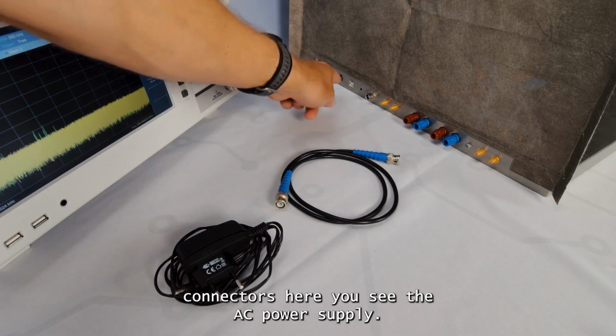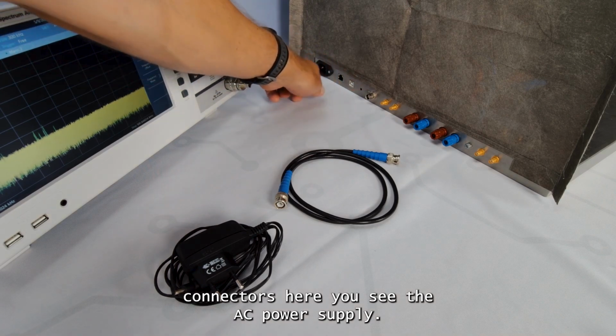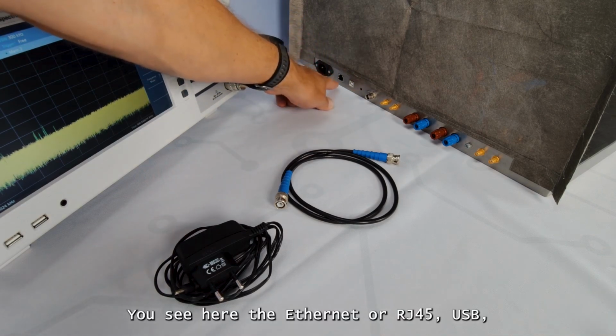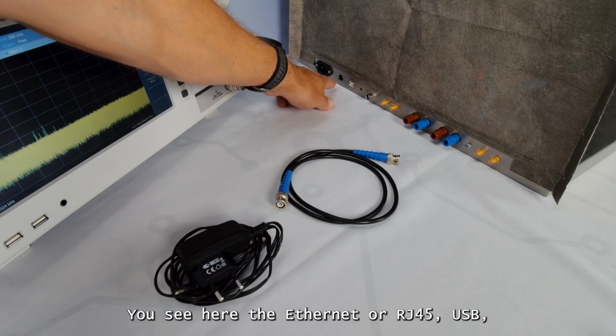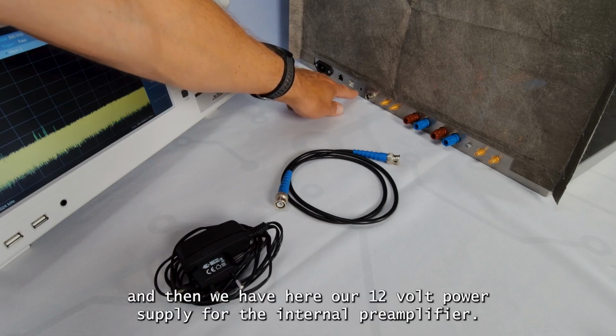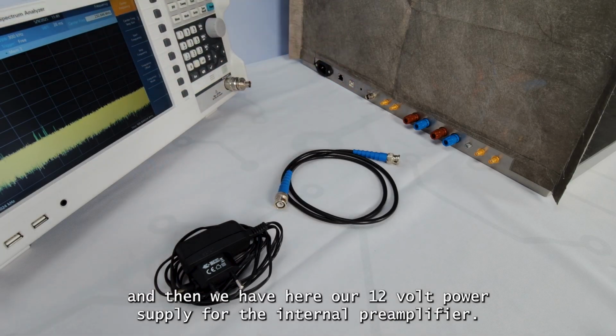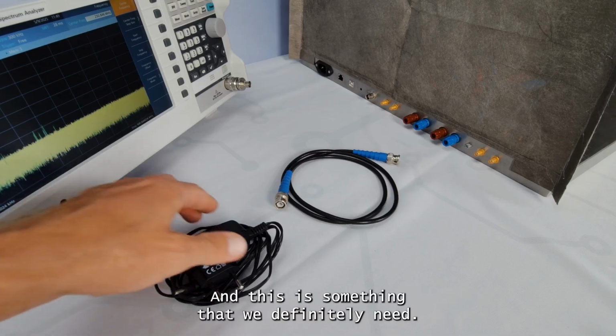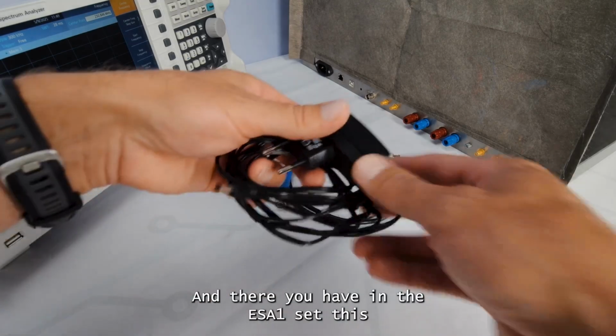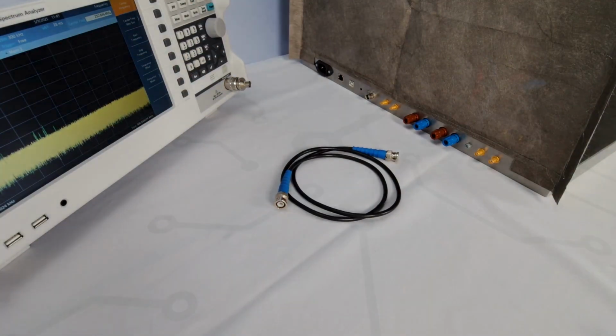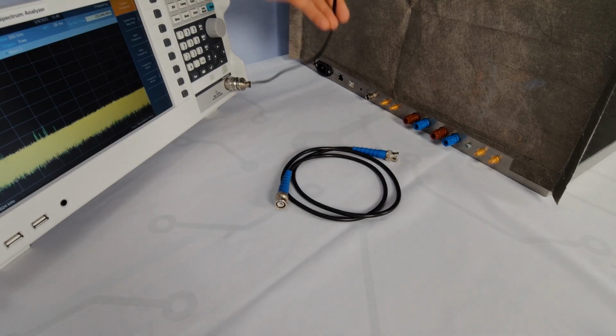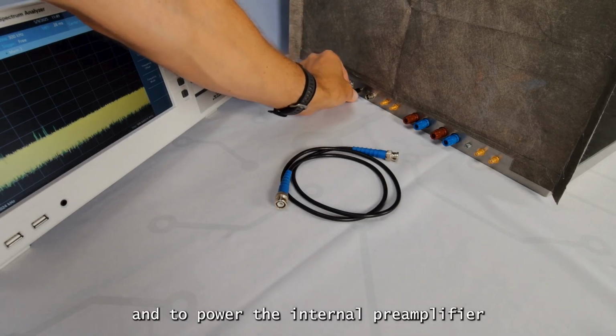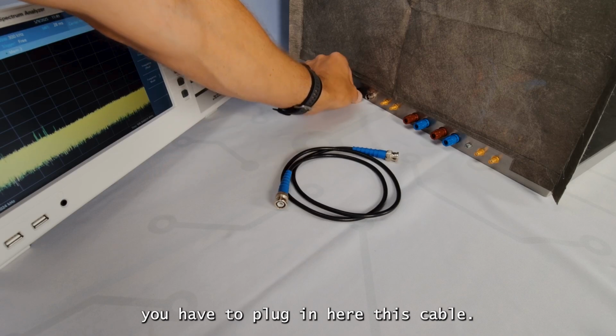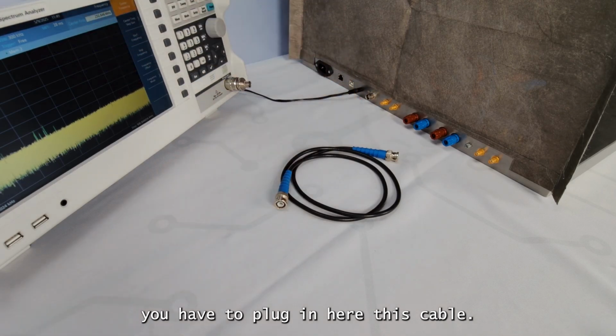For the connectors here, you see the AC power supply, you see the Ethernet or RJ45, USB, and then we have our 12-volt power supply for the internal preamplifier. And this is something we definitely need, and in the ESA1 set you have this power supply cable. To power the internal preamplifier, you have to plug in this cable.